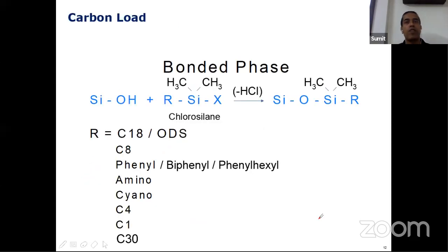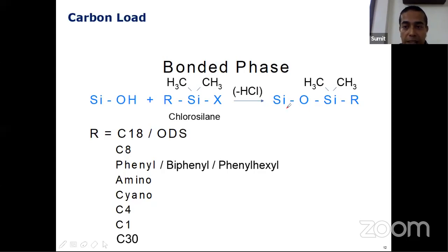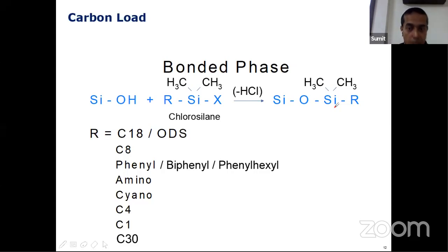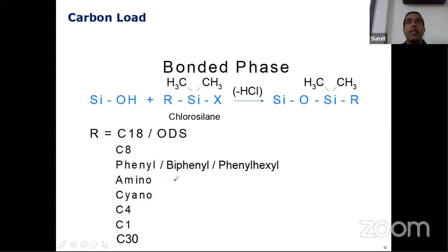To improve peak shape, people try to do something called adding a carbon load. What we've done is make the silanol interact — we synthesize a compound by making it react with a compound called chlorosilane. A hydrochloric acid group gets eliminated and you see a compound which is called carbon-loaded silanol. We can get various carbon-bonded chains: C18, which is typically known as octadecylsilane; we can also have a carbon chain of eight (C8); phenyl, phenyl-hexyl, amino, cyano, C4, C1, C30, and many others. We vary all of these because we try to improve our chromatography.